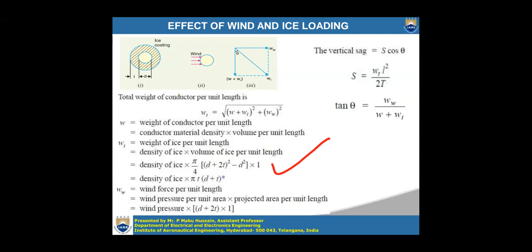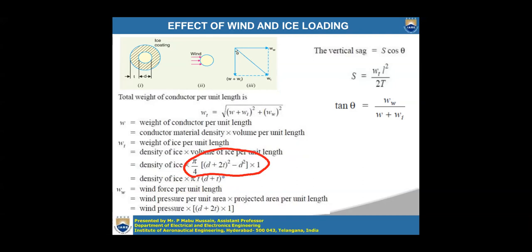From the first formula, you will get the second formula: density of ice × π t (d + t) by expanding the expression. Wind force per unit length of the conductor is also not always given directly — sometimes wind pressure per unit area and projected area per unit length are given, so you multiply those two. When diameter and thickness are given, wind pressure per unit length = wind pressure × (d + 2t) × 1. You have to remember all these formulas.